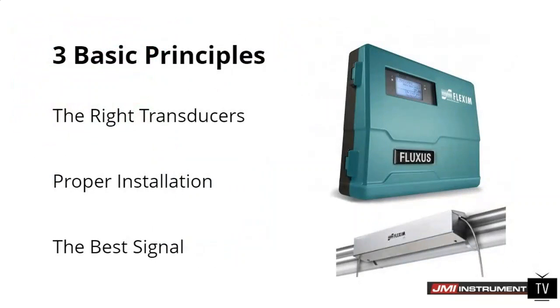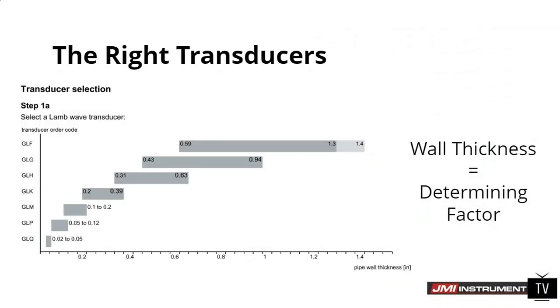So there are three principles we're going to talk about today to get a successful gas measurement. First of all, we have to have the right transducers. We have to do a proper installation. And when we look at our diagnostics, we want to get the best possible signal that we can get. So the right transducers really revolves around the Lamb wave type transducers that we use for gas. Lamb wave transducers are sized, the frequency is sized, by the wall thickness of the pipe. So it's matched to the wall thickness of the pipe so that we can resonate our signal on the pipe wall of the transducer. This allows us to get some longer signals through the gas, which is not very dense.